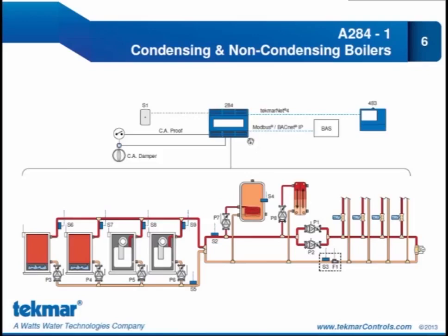Looking up top, I can see that I'm communicating with a building automation system using Modbus or BACnet IP. I'm also communicating to a Gateway 483 using the tekmarNet communication, which will allow for remote monitoring. I have an outdoor sensor to provide outdoor temperature reset. I'm also controlling a combustion air damper. And notice here that the end switch from the motor is connected back to the 284 to provide proof of combustion air, which is an optional feature on the 284.